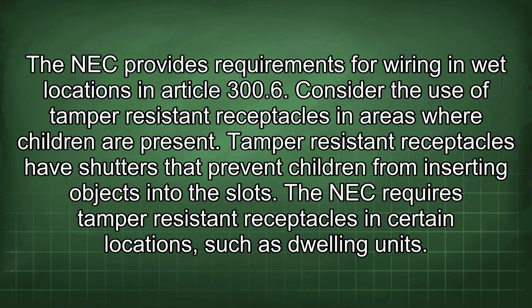Consider the use of tamper-resistant receptacles in areas where children are present. Tamper-resistant receptacles have shutters that prevent children from inserting objects into the slots. The NEC requires tamper-resistant receptacles in certain locations, such as dwelling units.